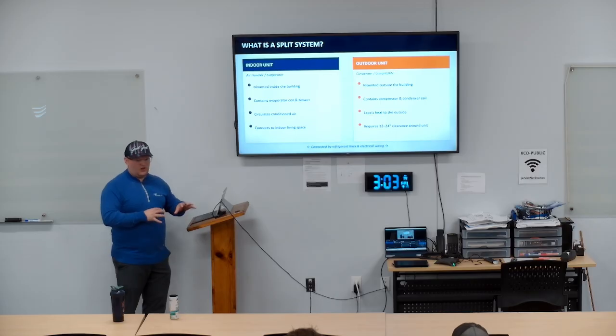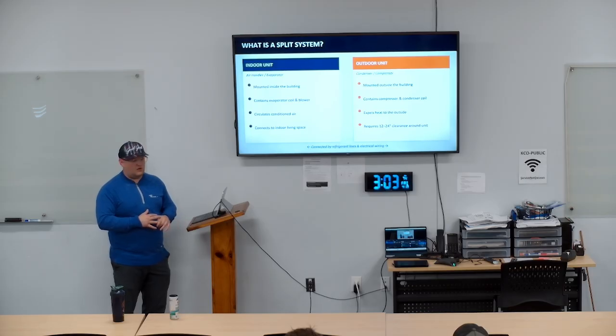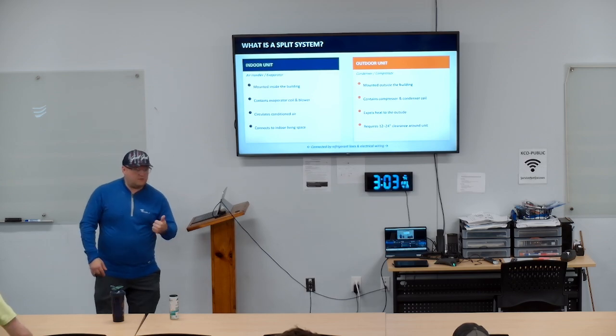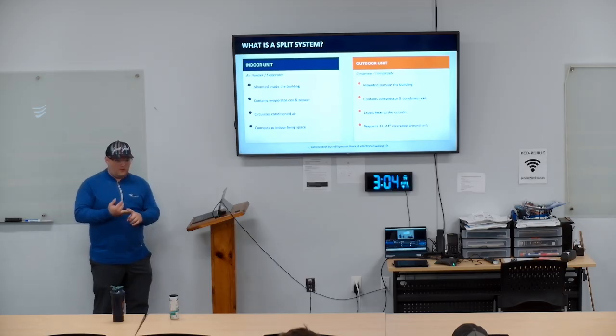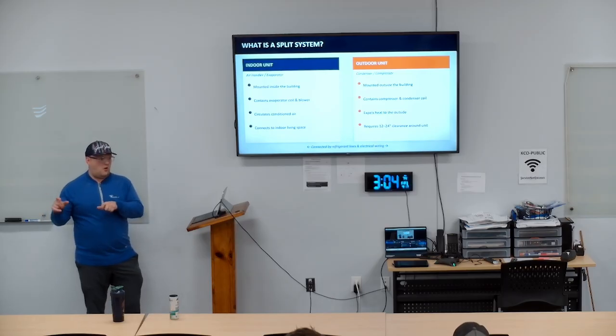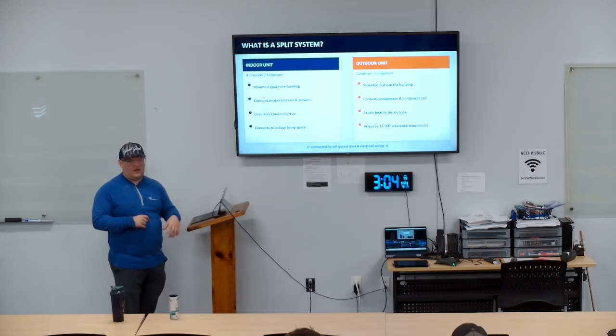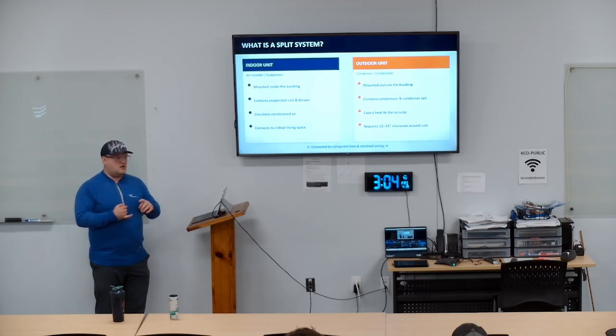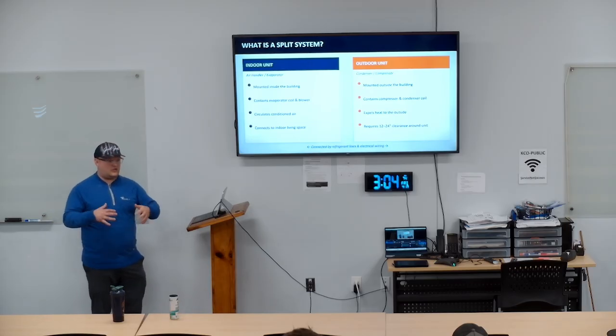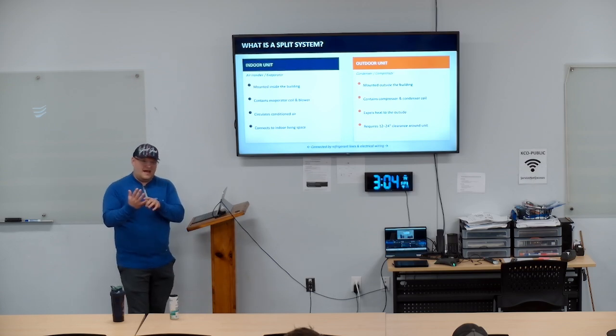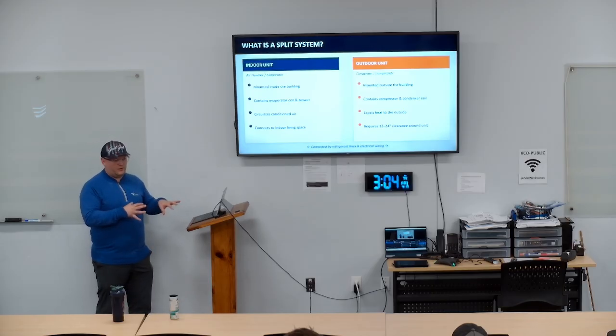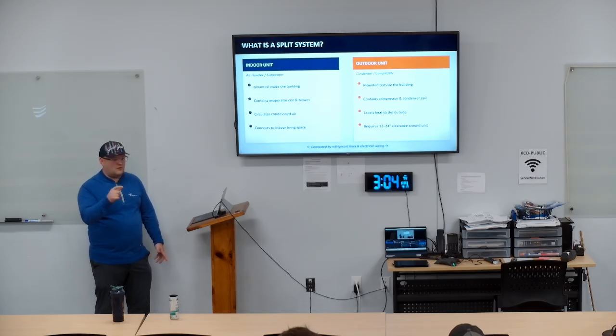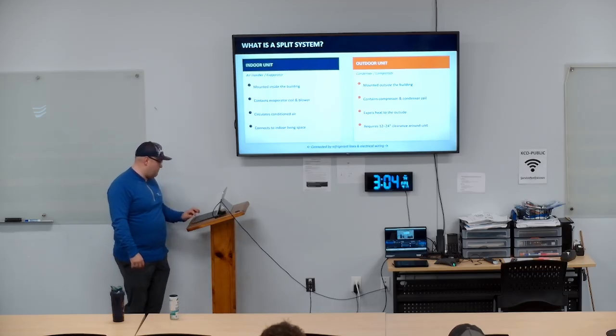All right, you're gonna learn real quick that the IOM is like your bible to units. And I know it's hard because on the PM side, you're asking for IOMs and normally you're getting submittals, not all the time you're getting IOMs. On our side, I'll see stuff on the submittal sheets and I still have to go to an IOM to figure out what I actually need. Because on the submittal, it'll say power is 208 or 230. Sometimes it'll say low volt communication, other times it won't. I won't know until I go to an IOM and actually look at the electrical panel. I will tell you, splits are so easy because they're labeled pretty hardcore. Inside a split, it's going to label this is an indoor to an outdoor, right on the board. So it makes it pretty simple. But we'll get into that some more.